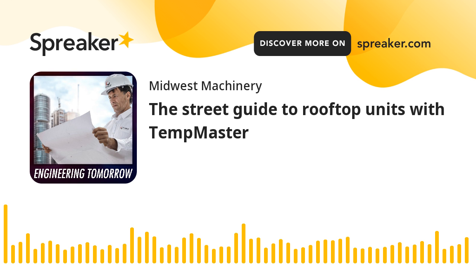So the Gateway is a great tool. It can be used for two things: startup and commissioning a unit and servicing a unit, or permanently attaching the unit to the Map Gateway. And before we get into that, really what the Map Gateway is, it's a little square thing. It's got a cable. You run it to the rooftop unit. You plug it into the control board, and it sends out a little closed Wi-Fi loop signal with the username and password.